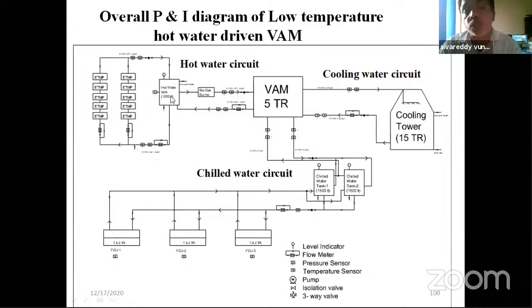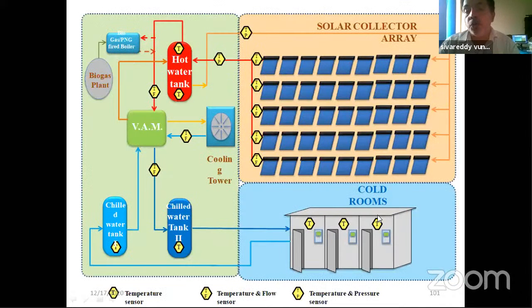Second thing, heat loss also. Suppose I store hot water at night time. Night time temperature is 20, hot water temperature is 90, so a 70 degree drop will take place and more heat loss will take place. For that reason, we kept the hot water tank only for surge purpose, but chilled water is for providing effective cooling in the cold room chambers.